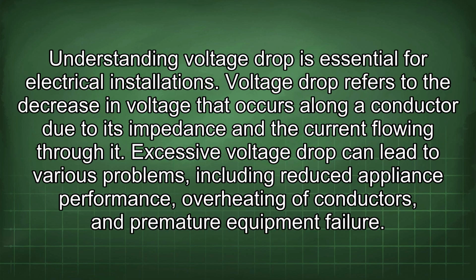Understanding voltage drop is essential for electrical installations. Voltage drop refers to the decrease in voltage that occurs along a conductor due to its impedance and the current flowing through it. Excessive voltage drop can lead to various problems, including reduced appliance performance, overheating of conductors, and premature equipment failure.